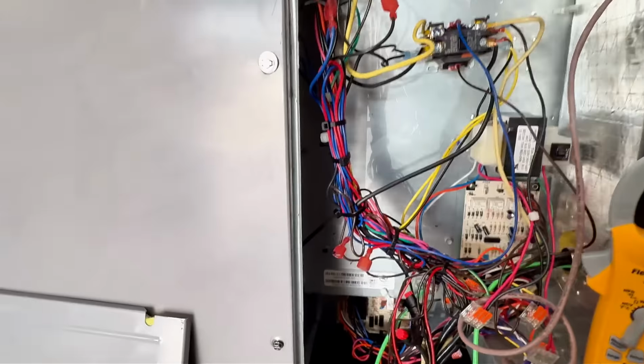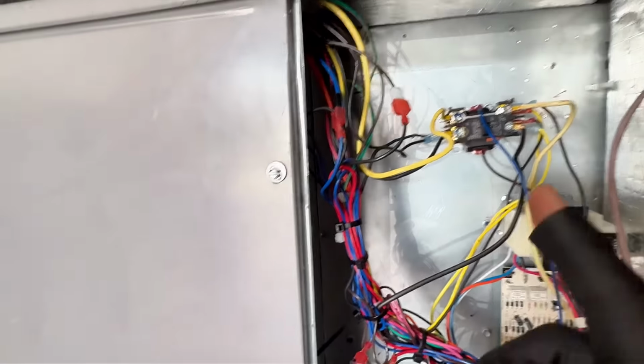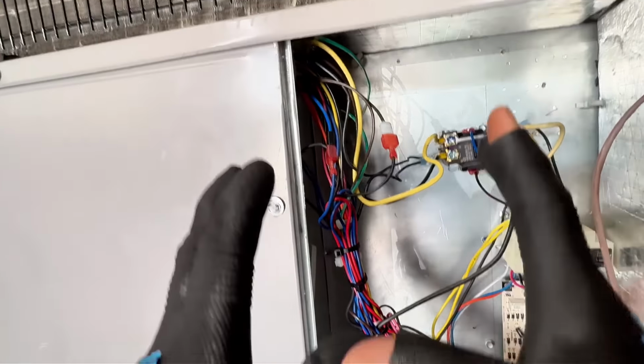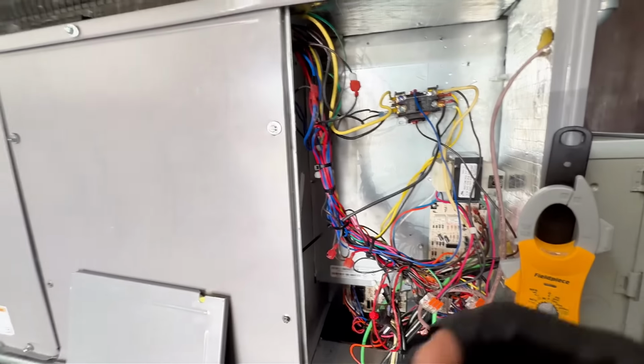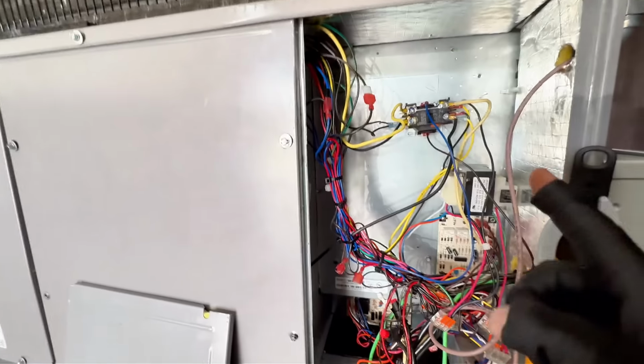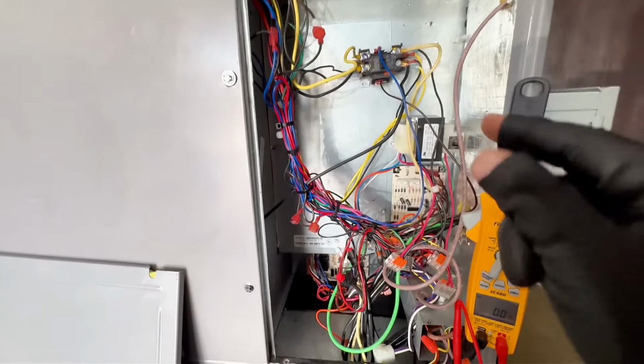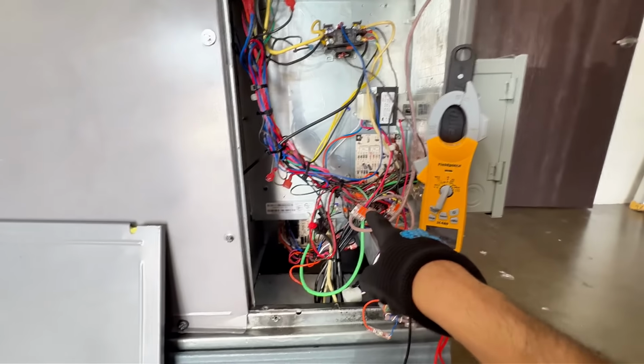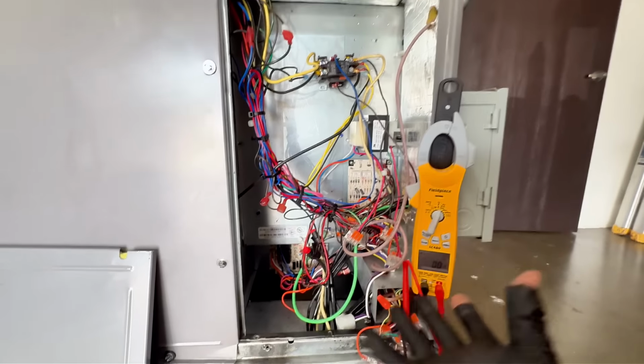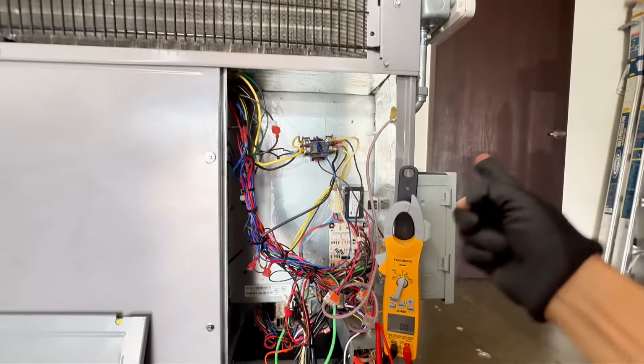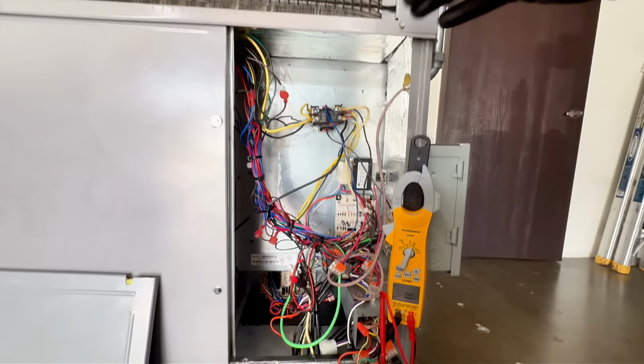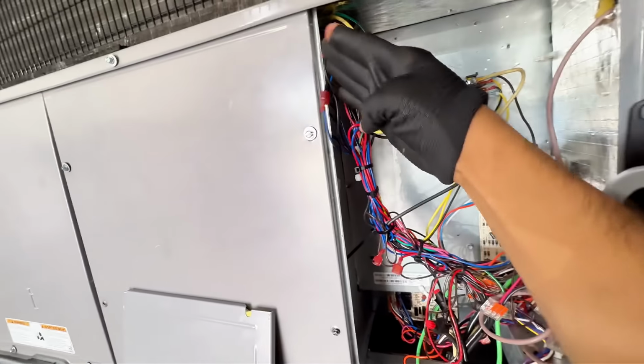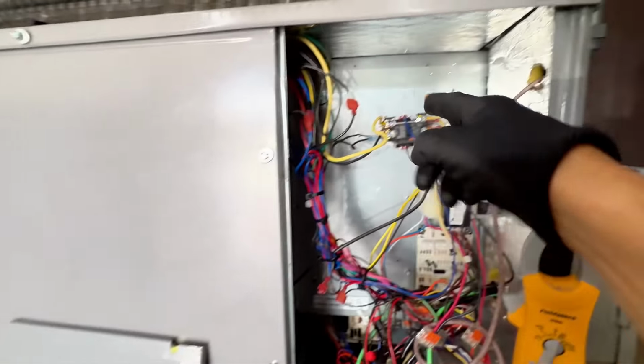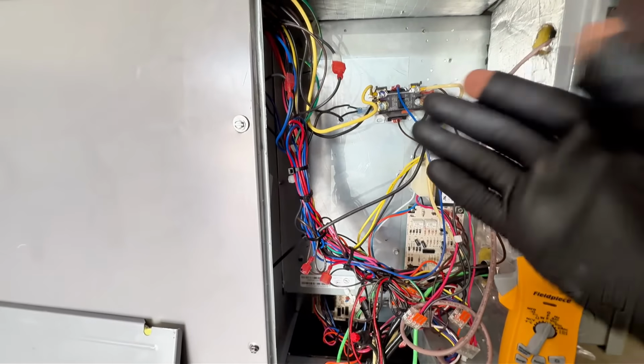I think at this point, what I'm gonna do, and this is where you can get a little bit kind of go everywhere. I know the path that the 24 volts takes: it goes from my unit, my 24 volts, to my thermostat, and it makes a jump to Y. Once I have a call for cooling, it goes through my pressure switches, and then it comes back to my contactor coil.